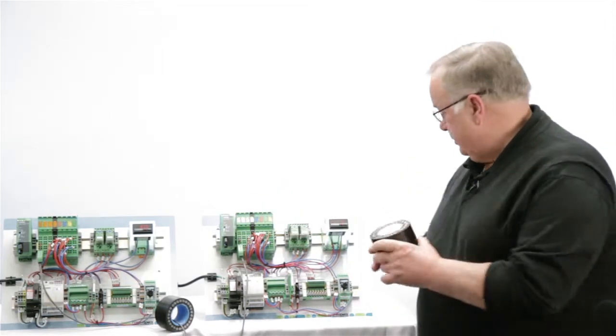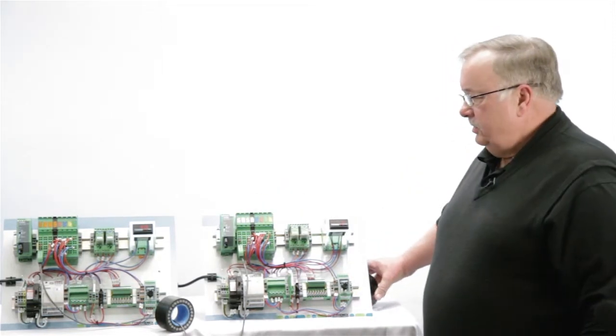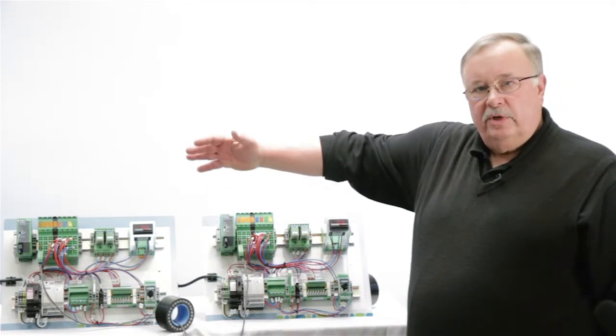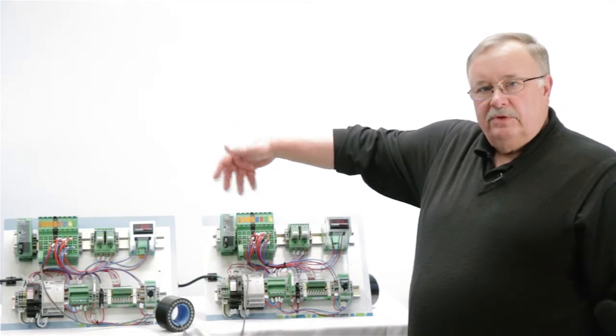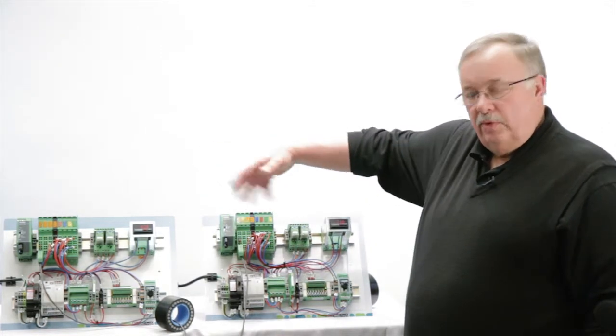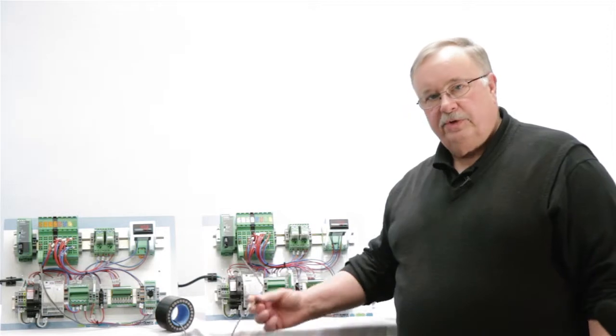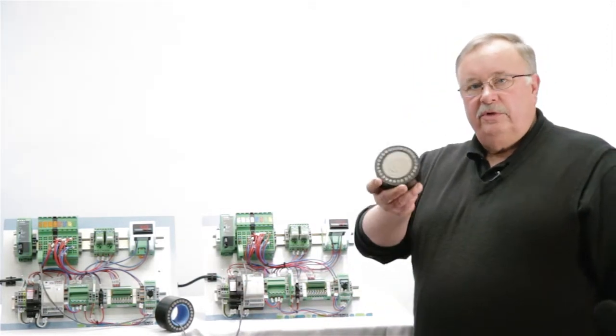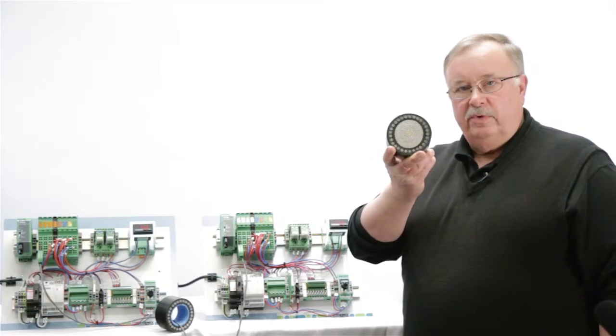This multiplexer system is designed to be a wire in, wire out, bi-directional communication, allowing discrete signals and also analog signals to pass both directions over a shielded twisted pair. The shielded twisted pair essentially can functionally do everything that this bundled cable can do as well.